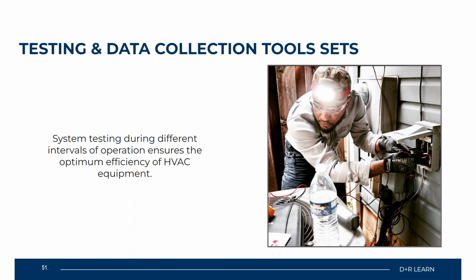Now, implementing control systems testing plans also creates a log of HVAC equipment operation. So, what you want to do when you are doing these different testing procedures is create some sort of a mechanical, or not even mechanical, but a physical copy of a log detailing all the different things that are occurring with that system. So in my experience, what I've found is that in mechanical rooms around the world, doesn't matter where you go, if you are some sort of a tradesperson, any mechanical room that you step into typically has a log book for certain pieces of equipment, such as a boiler or a chiller. And those logbooks will contain daily check-ins from whoever that technician was for the day that performed that daily routine, or even whatever type of maintenance it is as far as interval is concerned.